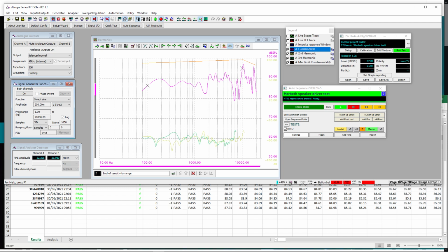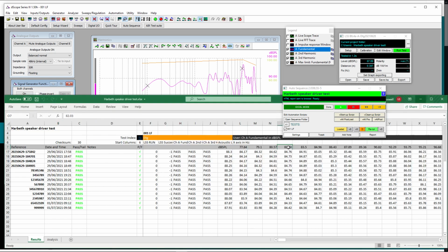So if we go through the columns in our spreadsheet, for example here, if we look at a column, we can calculate for that column a standard deviation. We can multiply that by whatever number, 3, 4, 5, 6, and so on, and then we can set that as the magnitude of the upper and lower limit.